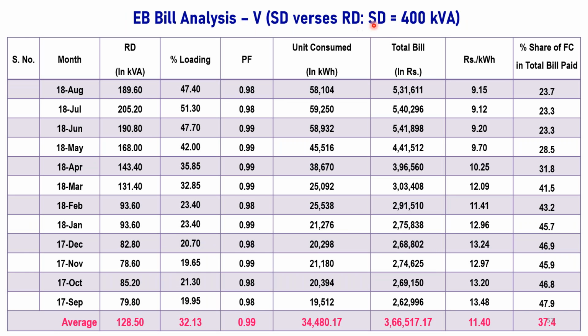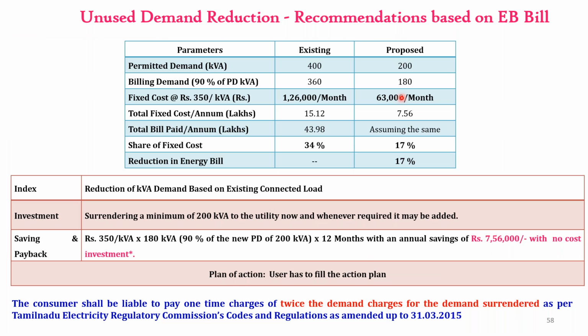And we recommended to surrender. Suppose the sanctioned demand is not utilized by the company and they do not have any plan to expand further, then we can recommend the company to surrender the kVA. It will also give a huge amount of saving for the company. So this is an example where the percentage loading is only 32%. The sanctioned demand is only 400, and this company does not have a plan for expansion. Initially they had an idea to expand, but they shifted the expansion plan to some other country. So they are still having 400 kVA, but we proposed reducing it to 200 kVA.